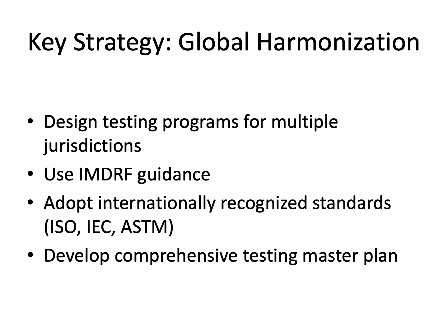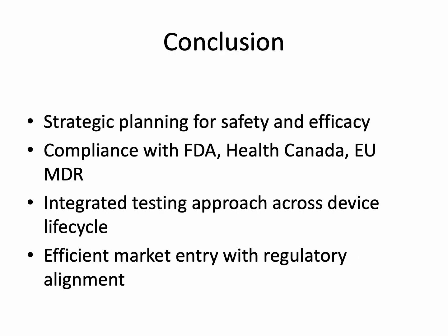Following International Medical Device Regulators Forum (IMDRF) guidance and internationally recognized standards like ISO, IEC, and ASTM enables simultaneous evidence generation for FDA, Health Canada, and EU MDR submissions. A comprehensive testing master plan outlines requirements for bench, preclinical, and clinical studies, minimizing redundancy, saving resources, and ensuring compliance across markets. Demonstrating safety and efficacy requires a strategic, structured approach tailored to the device, intended use, and target markets.